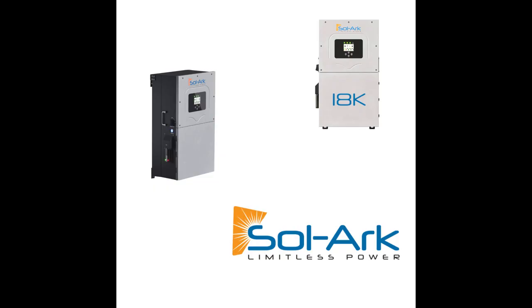So this is again the reverse, the economies of scale, right? For most businesses, it's really just the peaks that kill them as far as their bill. And it's really easy to get rid of those peaks. The deeper you dig when you're trying to offset more of their load usage, the harder it gets and more expensive it becomes. So again, typical use case, 1 and 2 inverters, 2 to 4 batteries, pretty small system, provides fast ROI, provides a lower overall energy bill, and can be done, again, with relative ease.